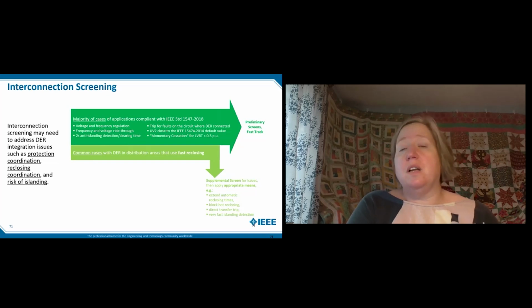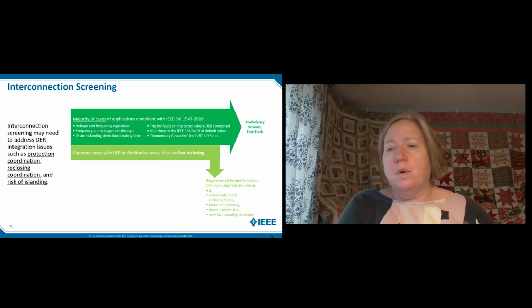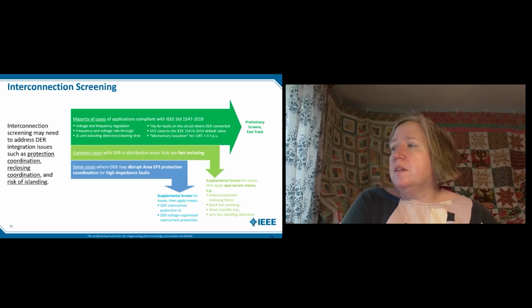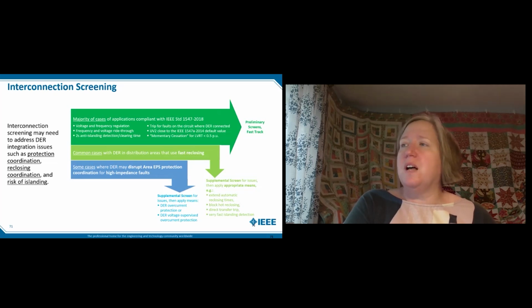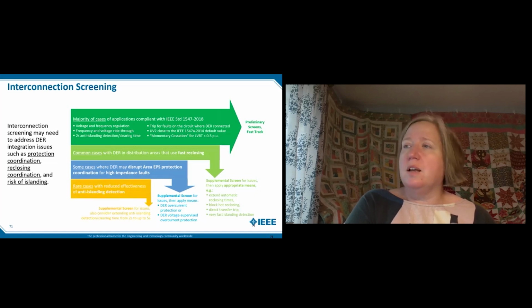If you use fast reclosing, and I can tell you I'm at a company that uses very fast reclosing on our first shot, we do a lot of hotline blocking, just so that we can make sure the feeder is dead before we close that breaker back in. And so you can run into something with your coordination for high impedance faults, which means you're going to be looking at the DER overcurrent protection, the voltage supervised overcurrent protection. And then you have cases where the effectiveness of anti-island detection is suspect. And that is the end.